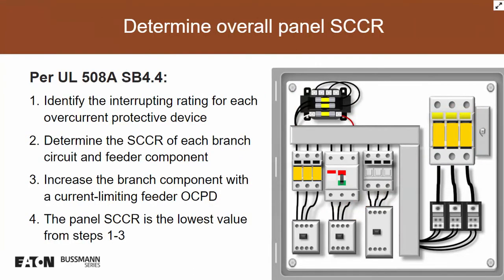All right, so in summary, we want to do a quick summary of what we covered. Step number 1 is to determine the minimum interrupting rating of all of our overcurrent protective devices themselves. So all the breakers and fuses that are in our panel on a power circuit, we want to look at their interrupting rating. That's what step number 1 is. If it's a 50,000 amp breaker that we have in there, the panel can't be higher than 50,000 amps. It could be lower based on step number 2 and step number 3, but it won't be higher than that.